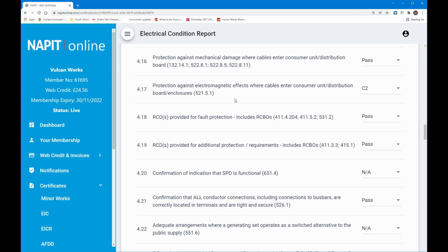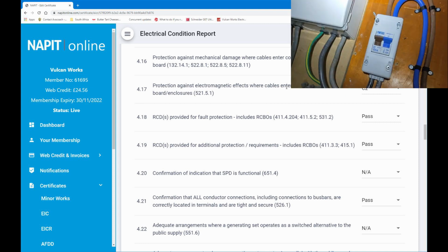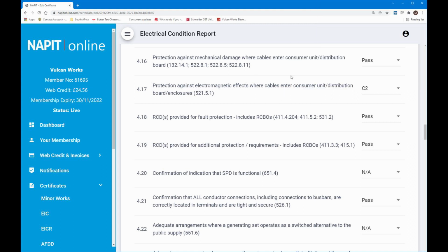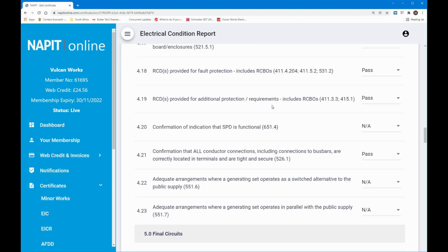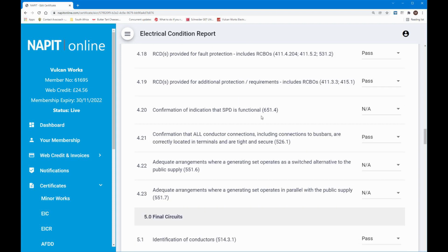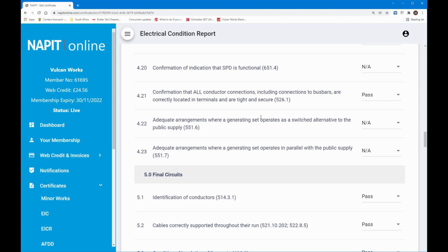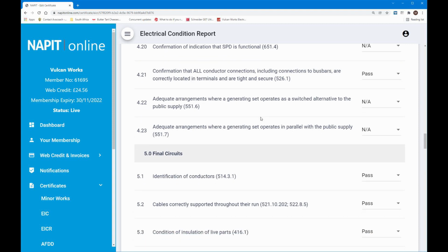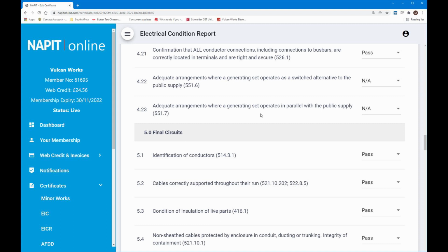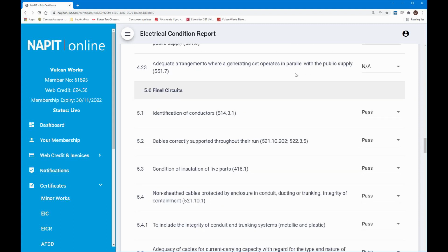This is the bit where it didn't pass. I'll quickly put up a picture in a second to show you why, but that's because the cables are going in different holes into a metal enclosure. That's wrong. So that is a C2. This is the major reason why this inspection failed. So that is what I've got to put right. The RCD is all passed. There's no SPD, so that's not applicable. That passed. There are no generating sets, so that doesn't matter.